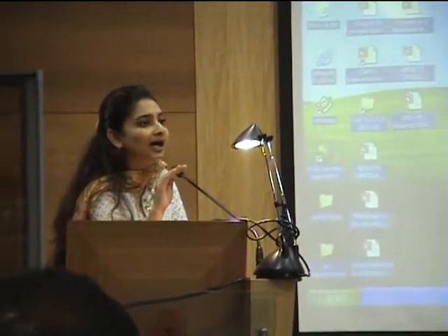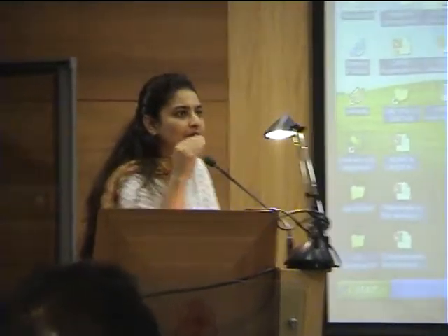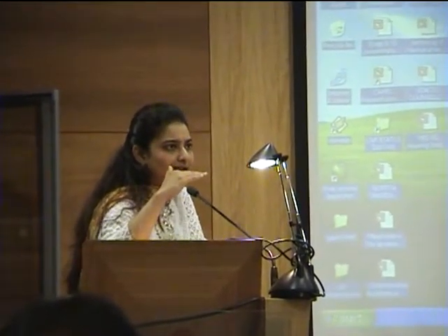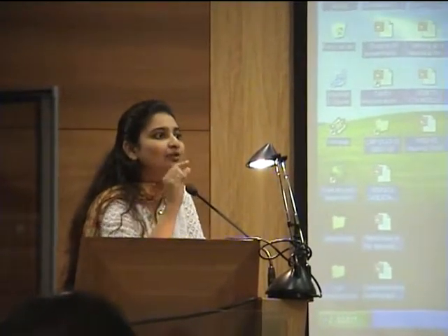And the second one is regarding if you could elaborate on pulse width and volume. You said pulse width is changed for loudness, and then the second thing you said is also volume. There are different ways of changing the loudness. Basically, volume works with your M levels or the C levels, where you are reducing or increasing; your M levels are set accordingly. Whereas, though your M levels are at particular current levels, by increasing the pulse width with the same M levels, you can get a louder percept.